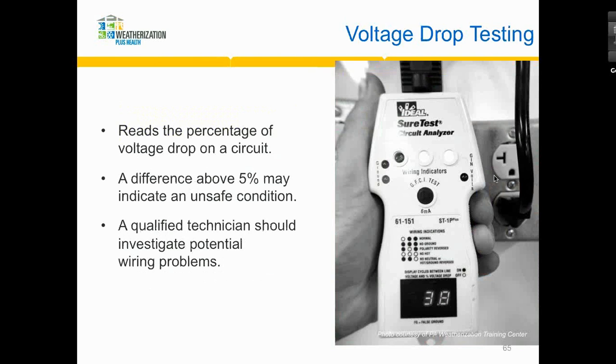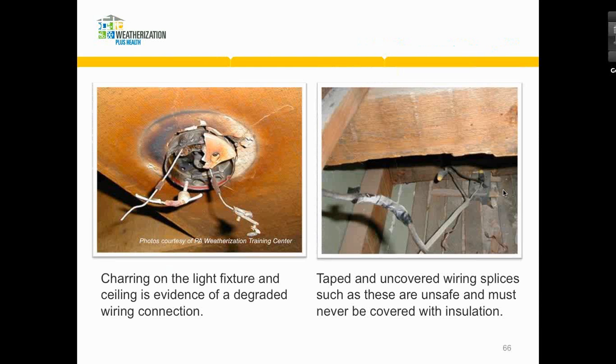We do a lot of safety testing. Electrical, this is a voltage drop tester where we find a lot of knob and tube wiring, which was innately very safe, but it's been kind of Mickey Moused over the years in most cases. No offense to Mickey Mouse, just saying. It's been added onto here and there, and circuits overloaded. So we test to make sure that if there is knob and tube wiring, that it's still safe. There are different guidelines around that. Suffice it to say, we do test it, and we see a lot of dangerous stuff.